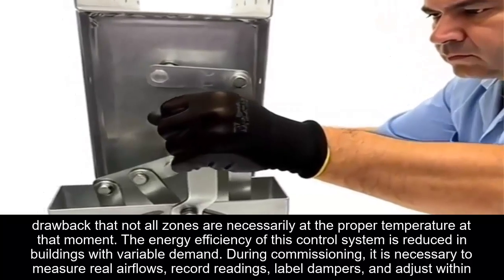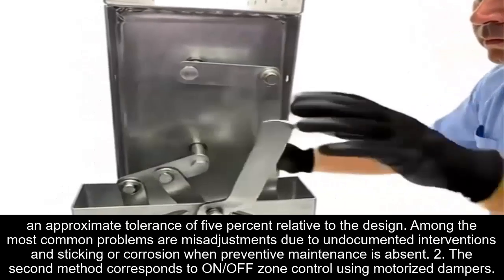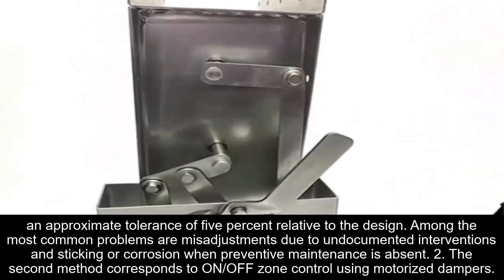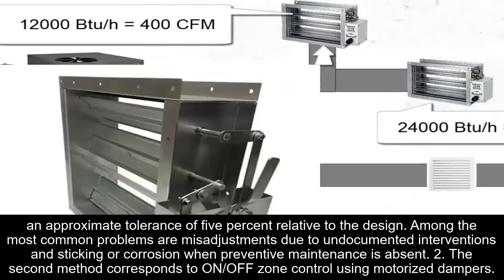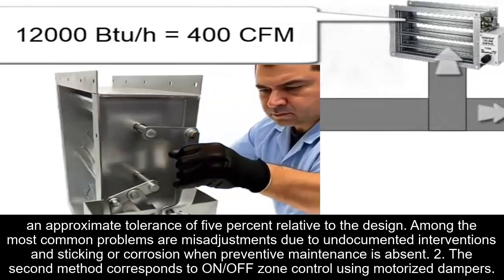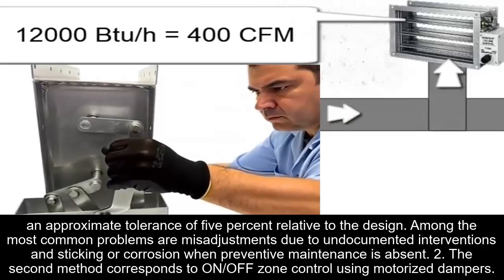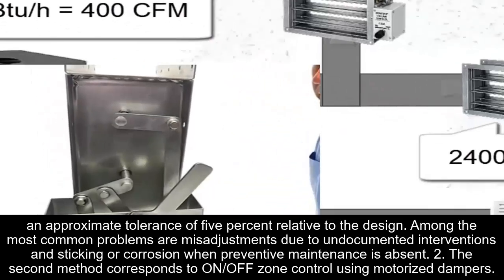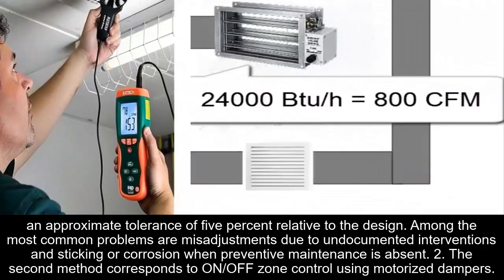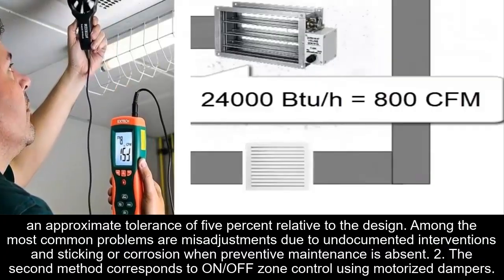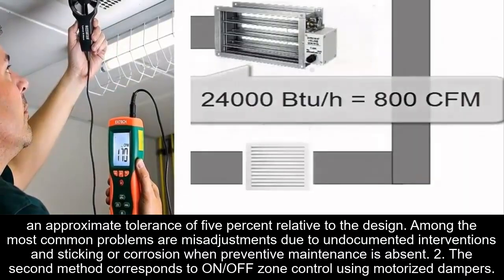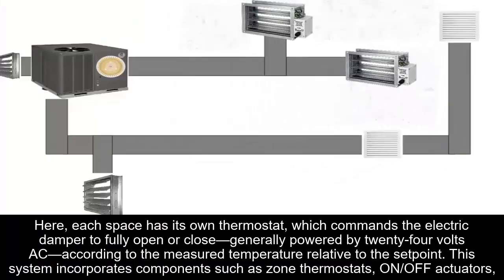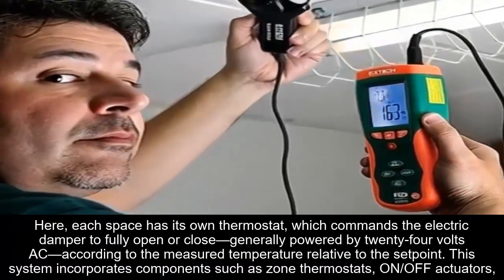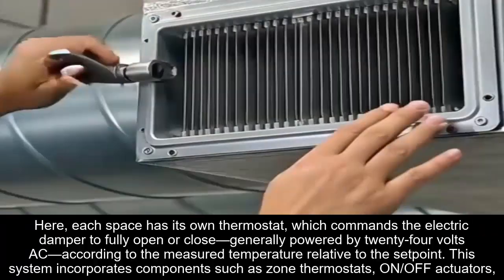During commissioning, it is necessary to measure real airflows, record readings, label dampers, and adjust within an approximate tolerance of 5% relative to the design. Among the most common problems are misadjustments due to undocumented interventions and sticking or corrosion when preventative maintenance is absent. The second method corresponds to on-off zone control using motorized dampers.